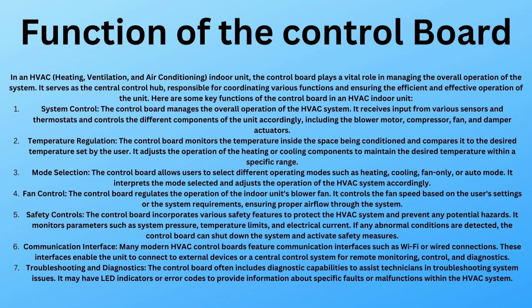Temperature regulation. The control board monitors the temperature inside the space being conditioned and compares it to the desired temperature set by the user. Basically, it has a sensor that monitors the temperature coming across it. That's why most thermostats are in the hallway, down by your return area, usually within the same proximity as your return air, because it pulls that air across the thermostat and then up into the return air, giving the thermostat the proper indoor temperature. With that, it adjusts the operations of the heating and cooling components to maintain the desired temperature within a specific range. That range depends on the user who wants a specific temperature for their home.